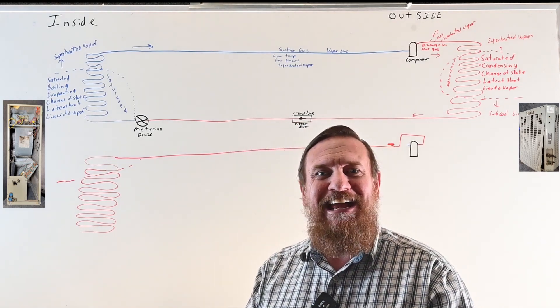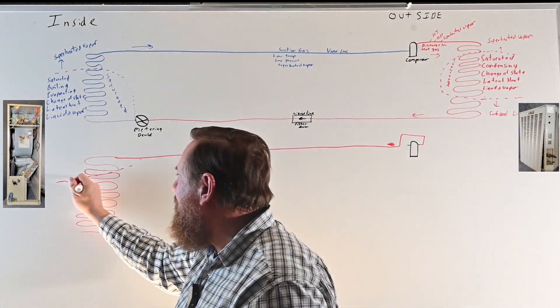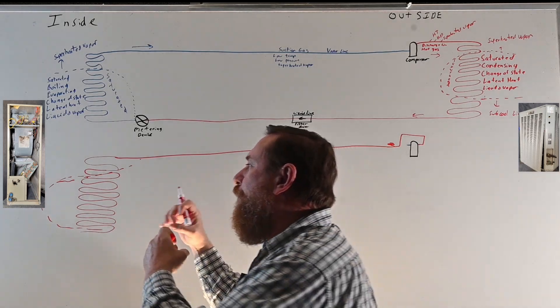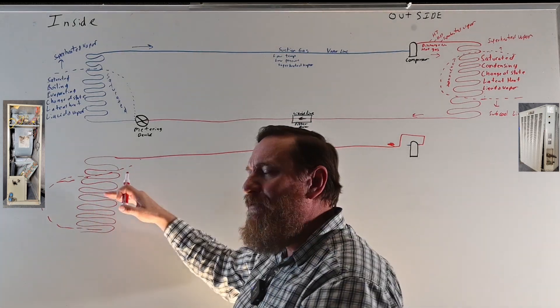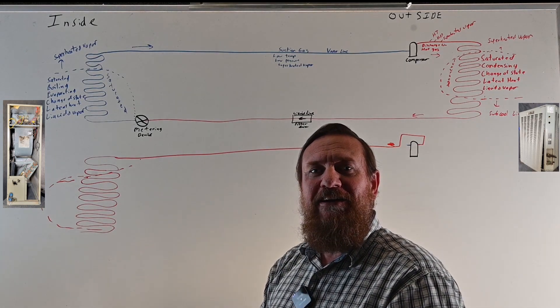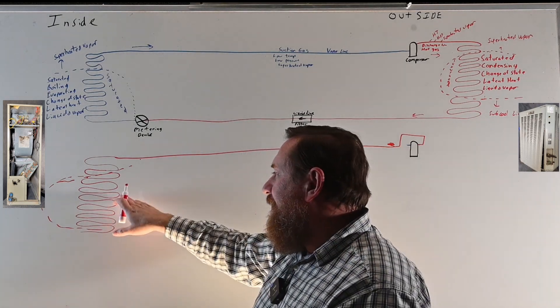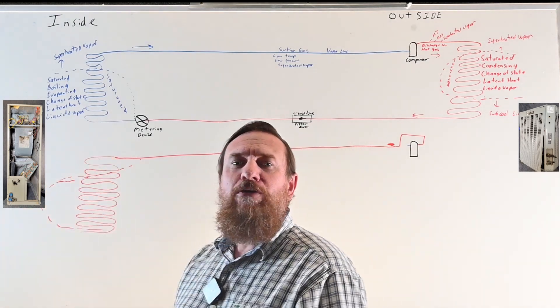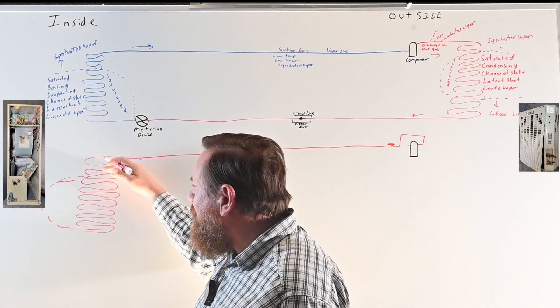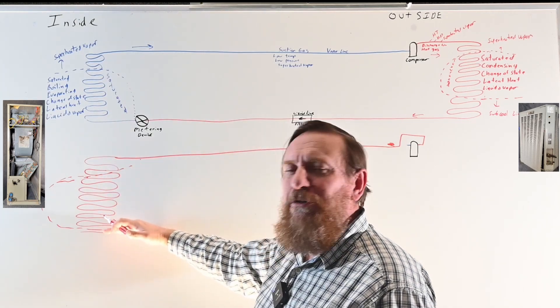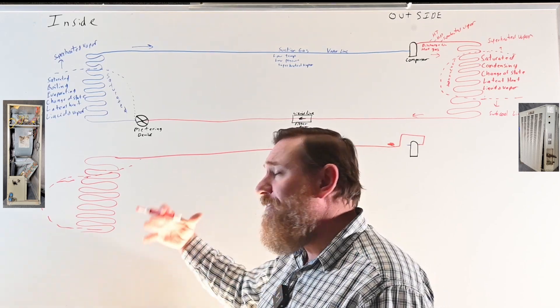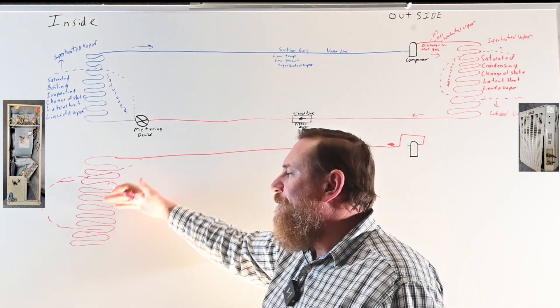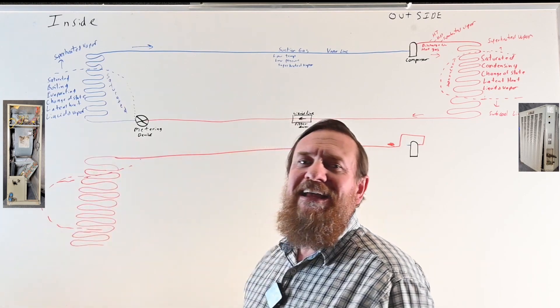That's where the magic of HVAC happens — a massive amount of latent heat is happening right at saturation. We're rejecting a ton of heat. The temperature of this coil is going to be higher than the temperature of the air in the house. If the air is at 70 degrees, this coil is at say 90 degrees, so heat leaves the warm refrigerant going to the cooler air, warming the air. After all the refrigerant changes from vapor to liquid, the liquid is still warmer than the air temperature, so we sub-cool it further through a few more turns of the coil.